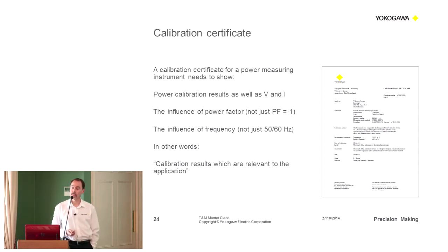Well, that's by calibration. So as I mentioned, there is a difficulty in this subject. Worldwide, nobody can measure. There's only one laboratory that can calibrate at 200 kilohertz, and that's in Sweden. 4 other standard national laboratories can calibrate at 100 kilohertz. And Yokogawa Laboratory in Amersfoort in Holland is the 5th. We can also calibrate to 100 kilohertz. So if you need to calibrate at the frequency of the application you're using, you basically need to go to a calibration laboratory which supports the frequency of measurement.